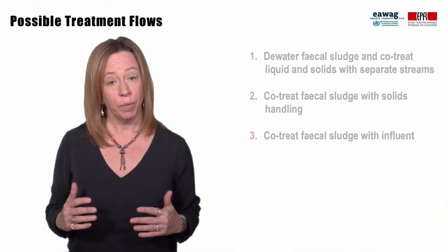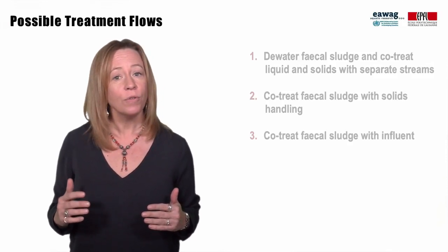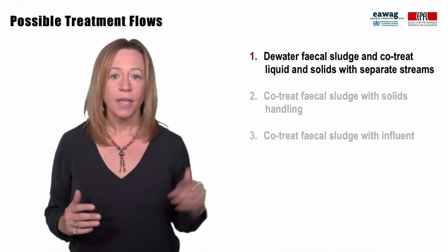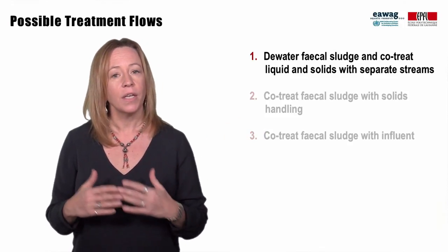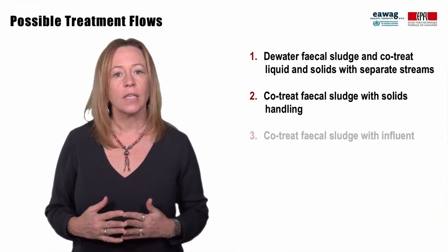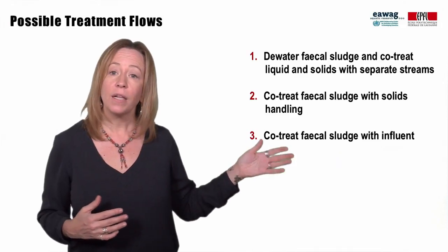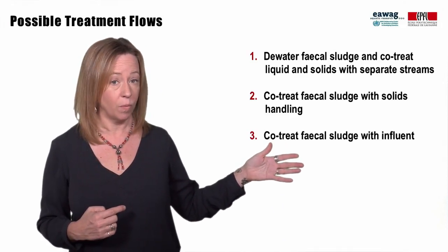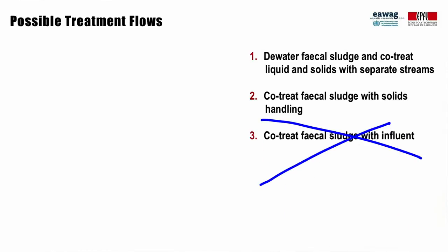If you have a wastewater treatment plant that is currently under capacity, there are three ways you could investigate co-treatment with fecal sludge. One: dewater the fecal sludge and send the resulting solid and liquid streams for treatment with the solid and liquid wastewater streams. Two: treat the fecal sludge together with the biosolids, starting from the dewatering stage. And three: directly treat the fecal sludge with the influent wastewater. In general, three is not recommended, and it needs to be stressed that fecal sludge should never be added directly into secondary wastewater treatment.